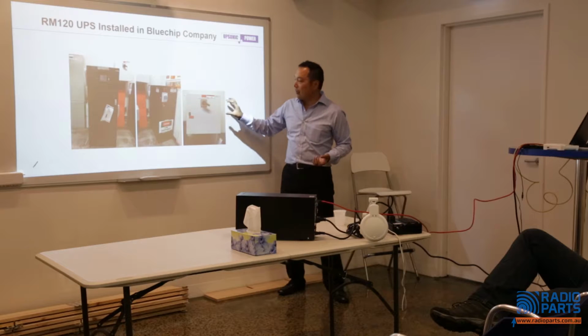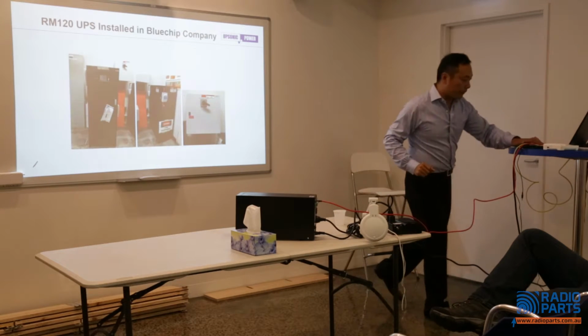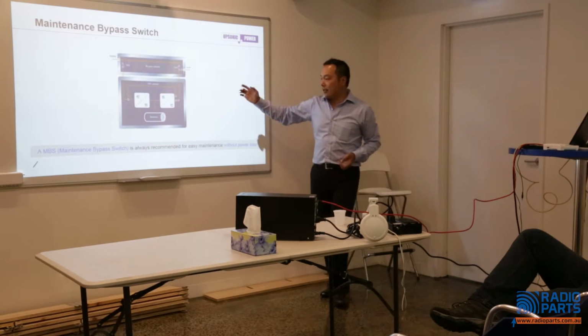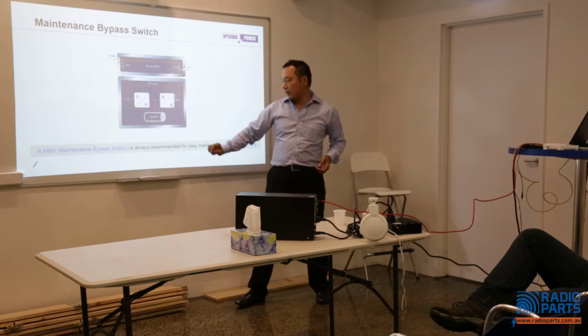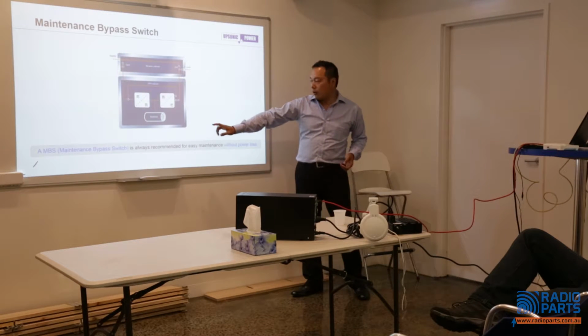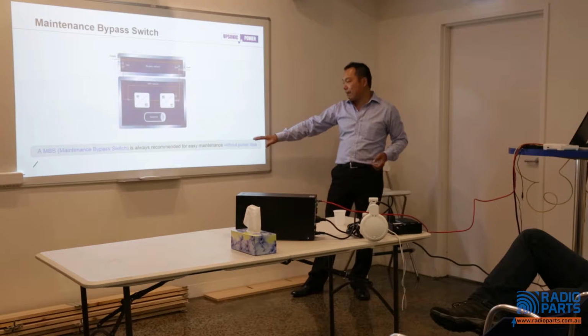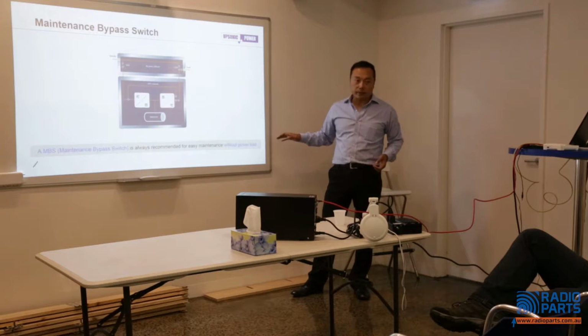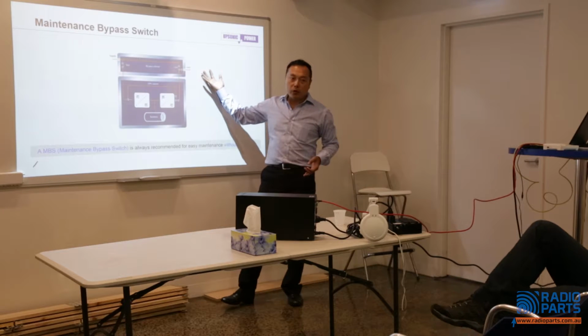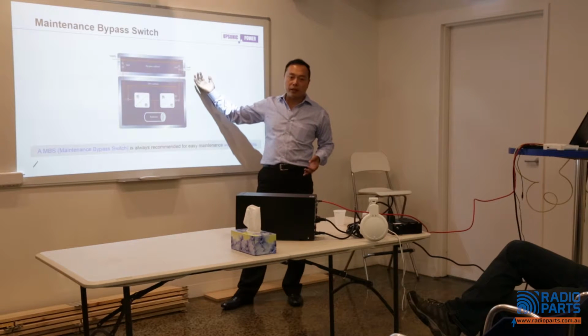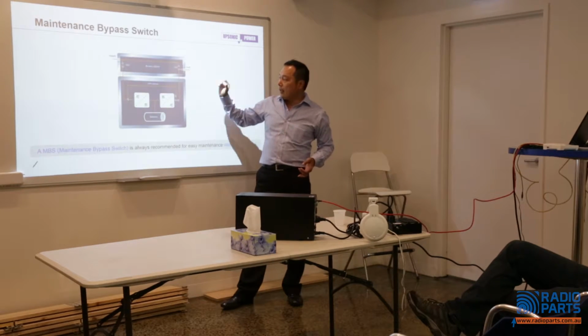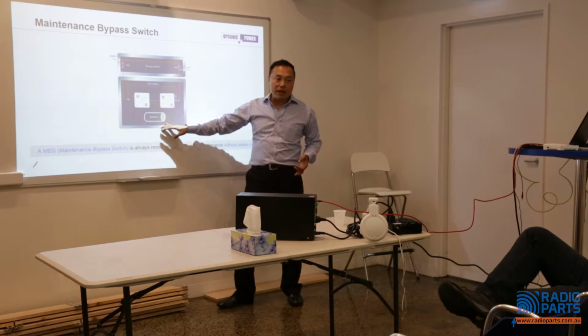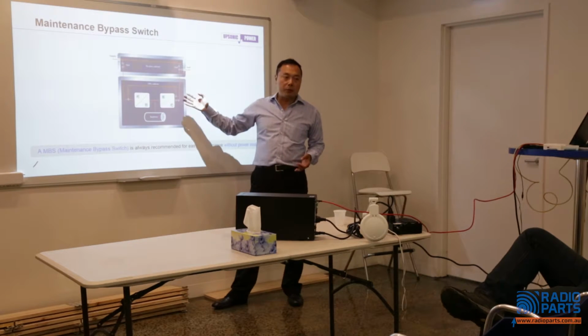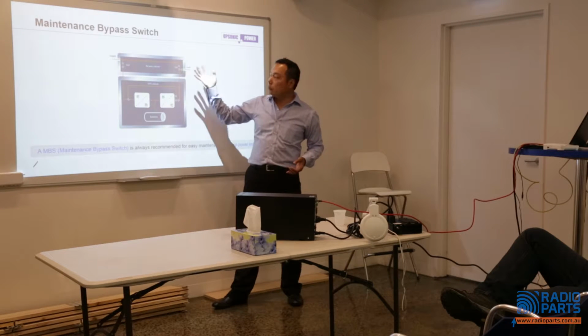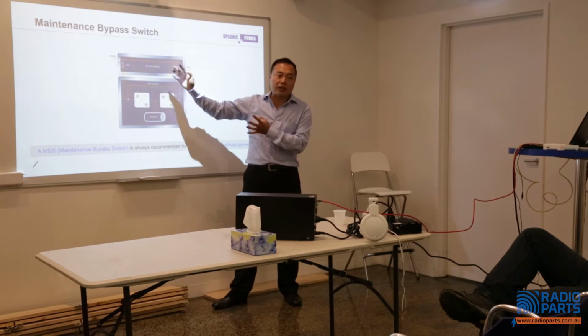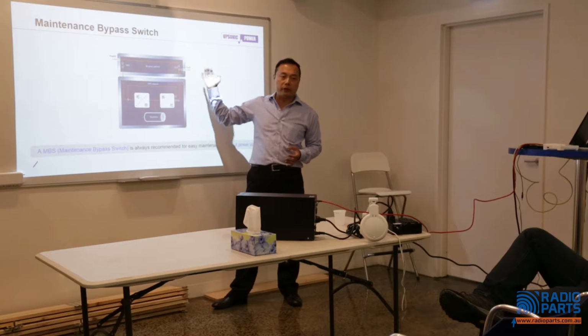So why do we need this maintenance bypass switch? Here explains why we need it. It's always recommended for easy maintenance without power loss. Suppose you are powering an important load, could be a server, could be in the data center, and if you want to do maintenance or repair of the UPS, you don't want to lose power.